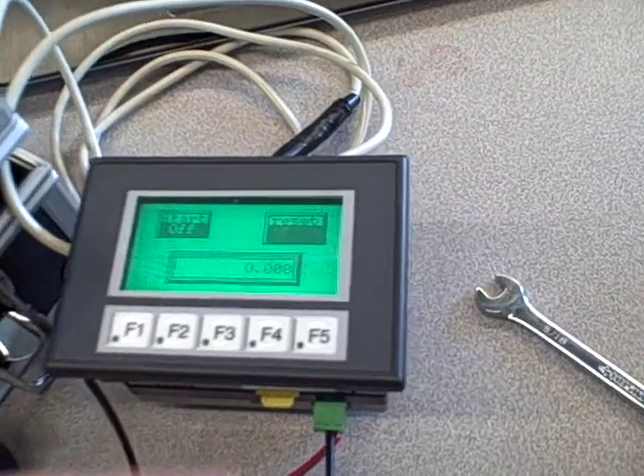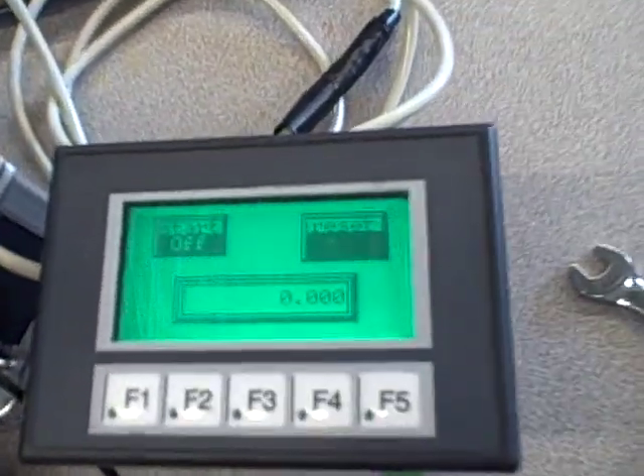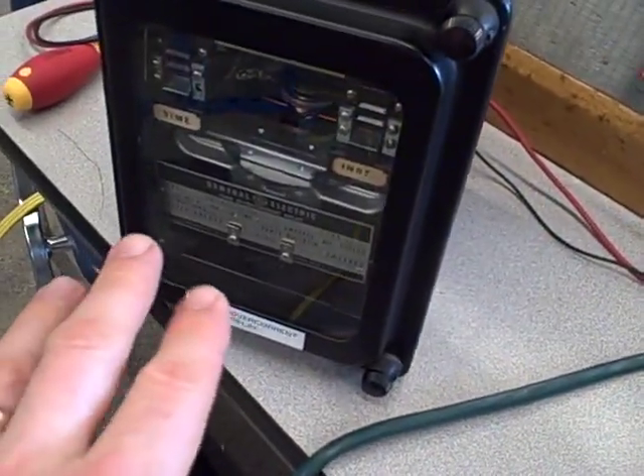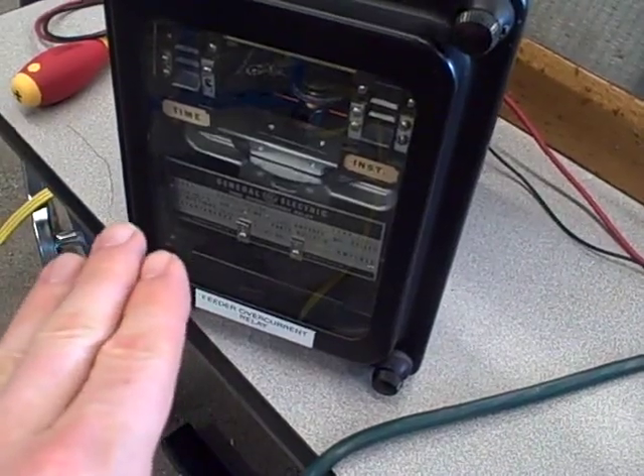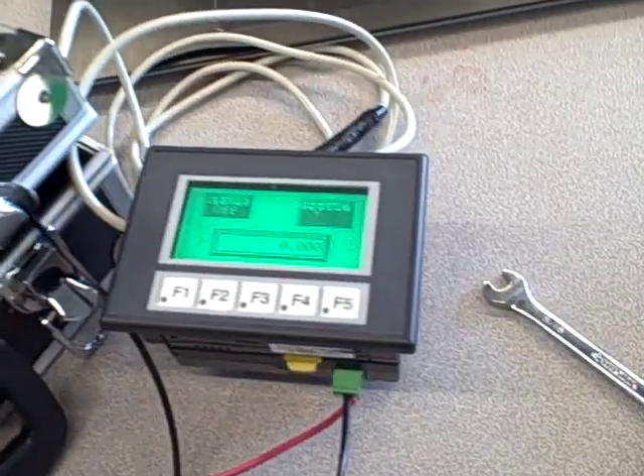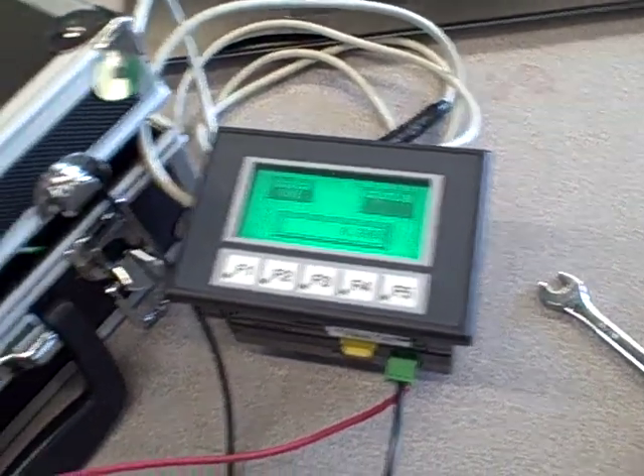The PLC will register when the power is applied and it will begin rolling the timer. And then as soon as the protective relay reaches the end point and the contacts close to trip the breaker, that's going to command the PLC to stop timing.